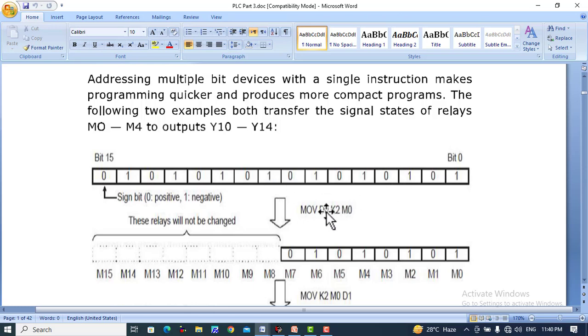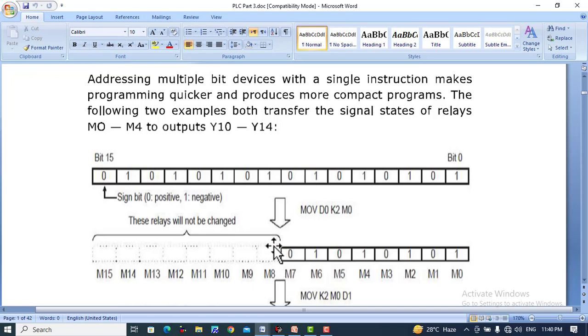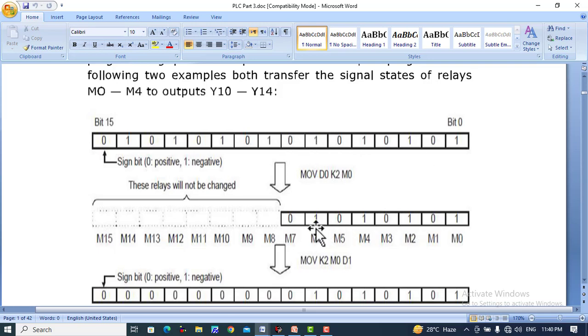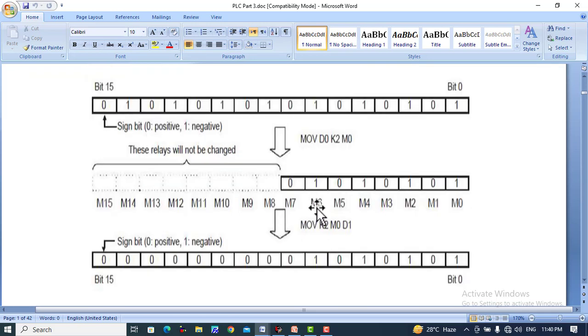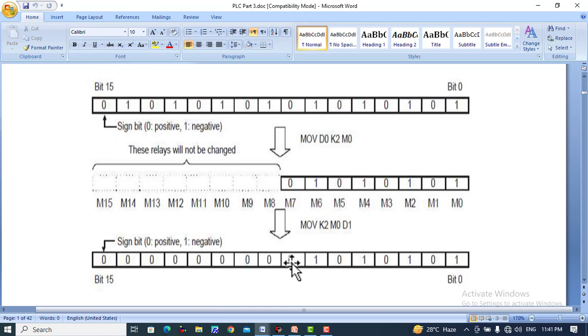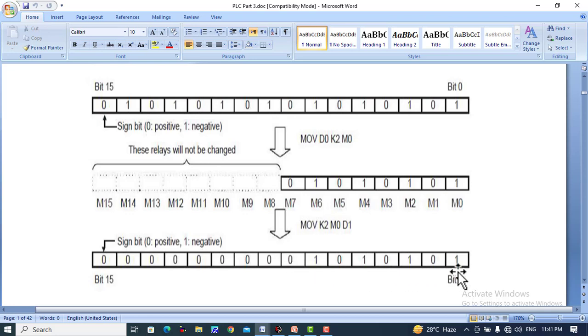The 16 values from D0 will be transferred to M0, M1, M2, M3 up to M7. The other values will be discarded, and relays beyond M7 will not be changed because K2 selects eight numbers. Similarly, MOVE K2 M0 D1 moves eight relays from M0 to M7 to D1. D1 is a 16-bit register, so values will be written up to bit 7 (M7), and the remaining bits will not be changed.